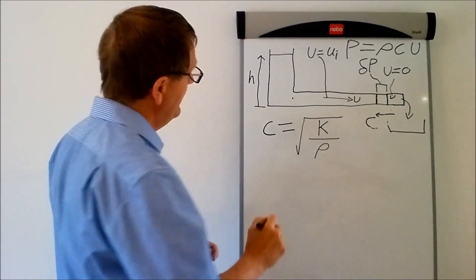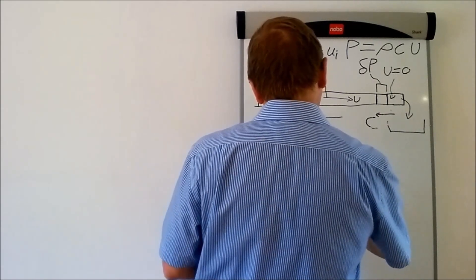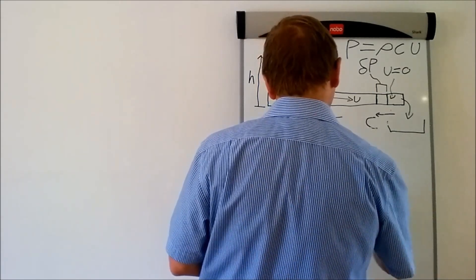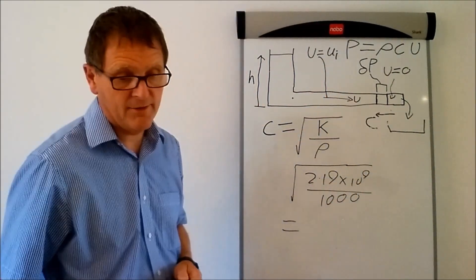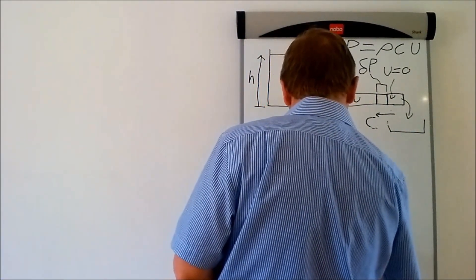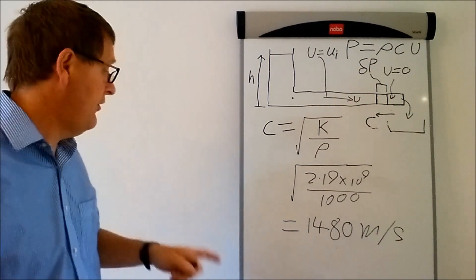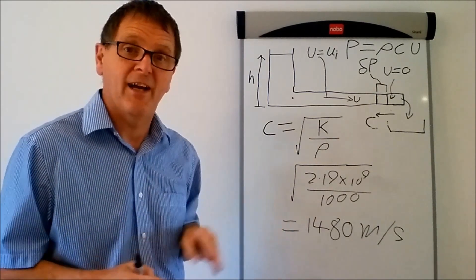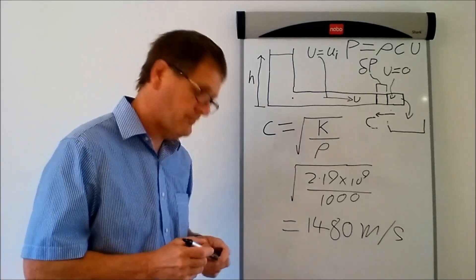For water, the bulk modulus is approximately 2.19 × 10⁹ Pa, and the density is 1000 kg/m³. If you calculate that, it comes out at 1,480 metres per second. That's the wave speed if the pipe was perfectly rigid. But it's not perfectly rigid — the pipe flexes, and the pipe flexing can make quite a big difference to the wave speed.